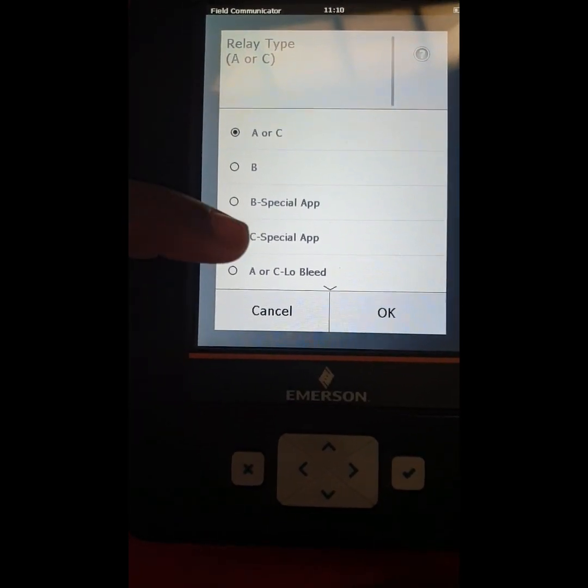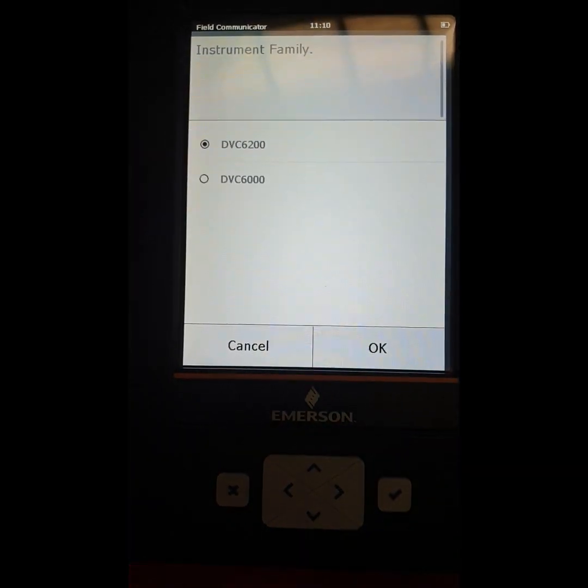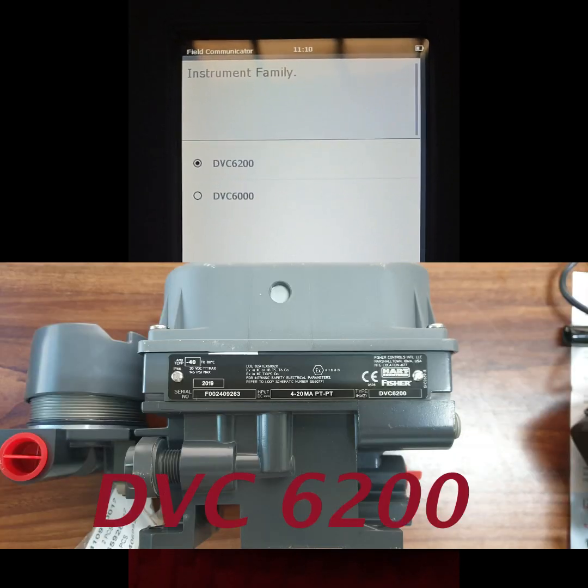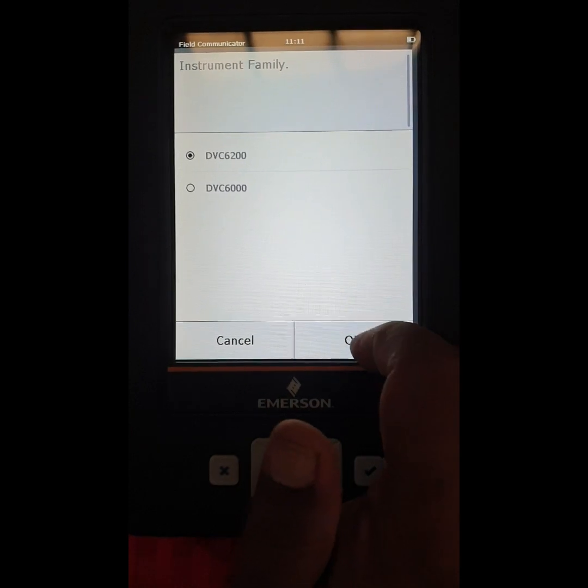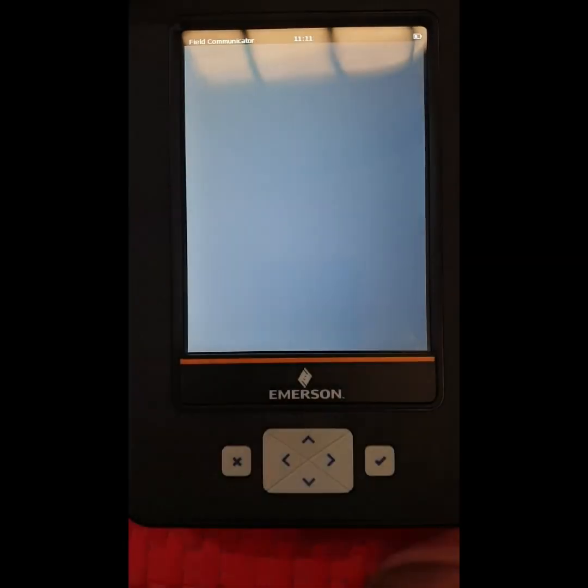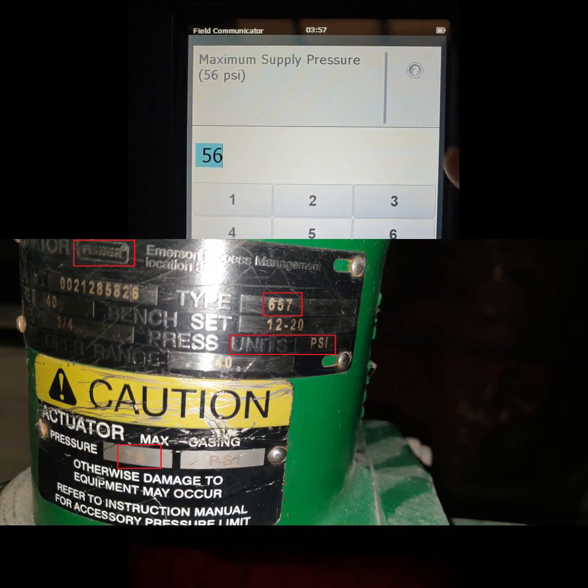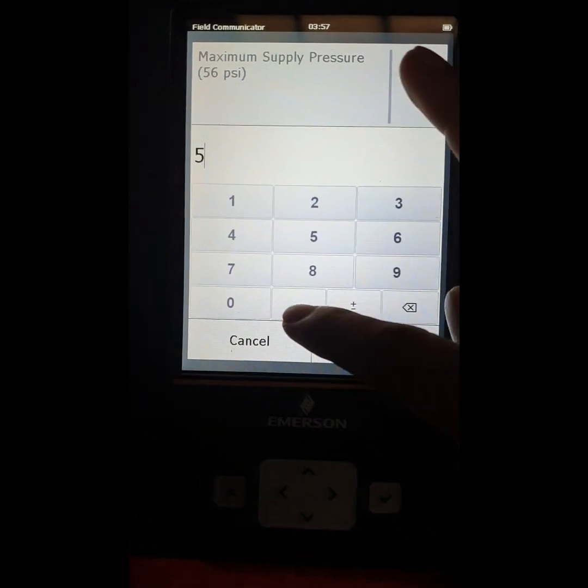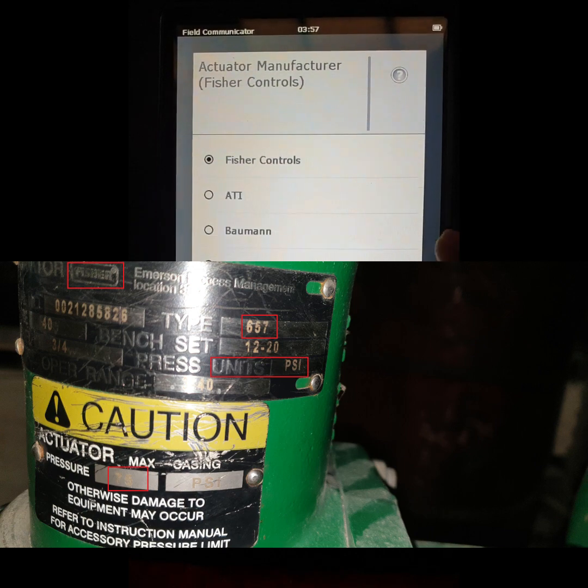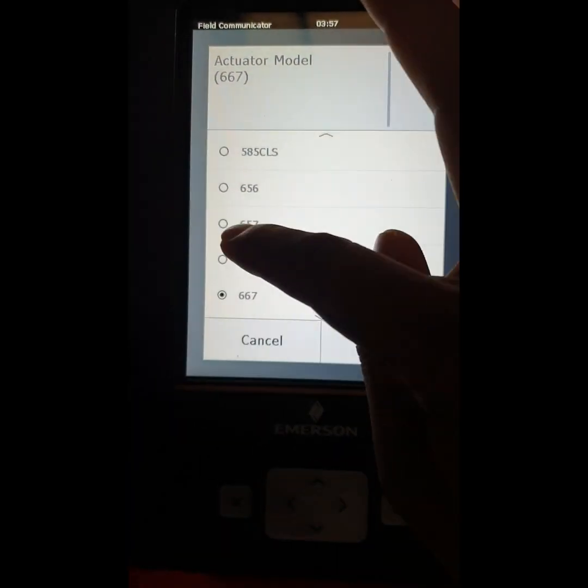Press OK. They are showing the positioner model number — our positioner is DVC6200. We select this and press OK. It is travel control. The pressure unit of the actuator is PSI and we set the pressure to 55. Our positioner is Fisher Control, so we select Fisher Control.